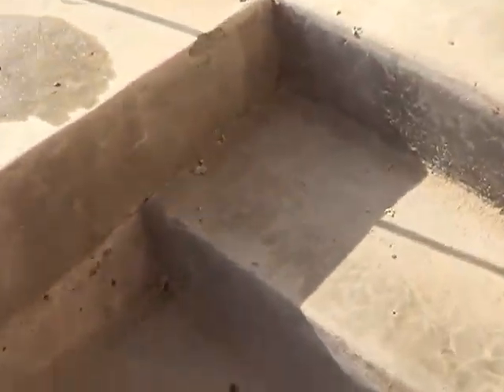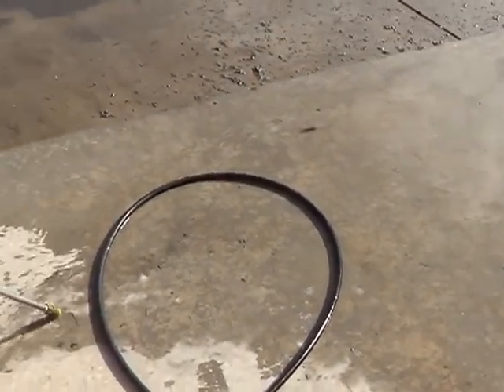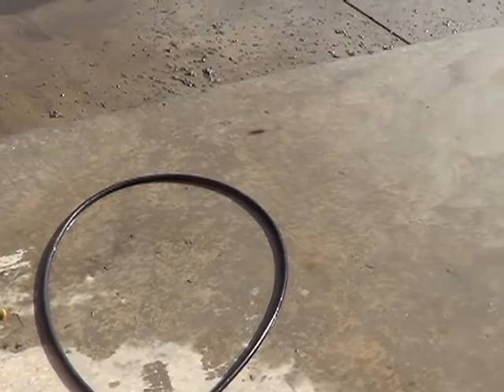That's 2 of them. This is the mess you get. Now I'll put them back in and pull the 2 out on the other side. This is the kind of stuff you should force your kids to watch. You know, it's one thing when it's a water feature at home and you do it once or twice a year, but this needs to be repeated as often as necessary. Otherwise, it starves the suction side of the pumps and they'll cavitate. And if you don't stay on it with this side, what passes through gets caught in the other strainers, and those are a big job. This I can do with the system running. The other ones I have to shut down a chiller and do the Y strainers, and they're 12-inch by 24-inch, something like that.